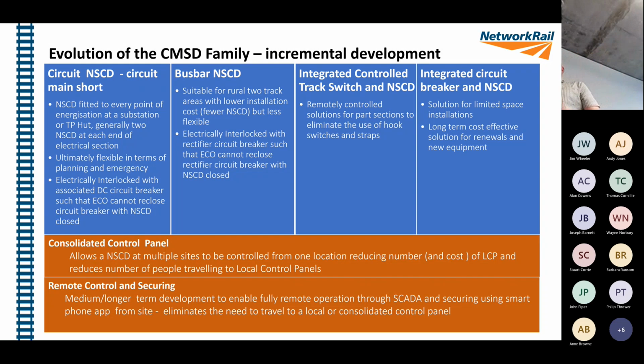Ultimately, we want to have remote secure, where we'll be able to lock out the SCADA system and lock the ECO will operate the NSCD, and we'll be able to protect that with a phone to stop the control of the ECO being able to recharge. But we're not waiting for that. The fact that we're 73% in Wessex, we've saved tens of thousands of straps being fitted on our infrastructure, and each of those straps we saved is potentially someone getting it wrong, putting themselves at risk. If we'd waited for utopia, we wouldn't have even started.